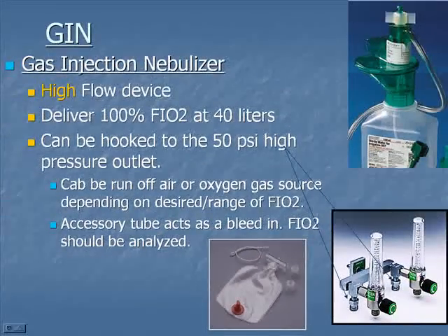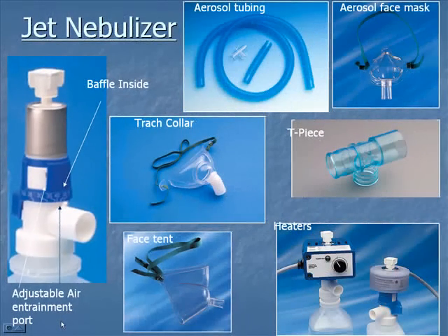Without a collection bag, water builds up in the tubing and will actually spit out of the jet nebulizer port onto the floor. Water spitting out indicates back pressure — the floor can be soaking wet if the tubing hasn't been drained. You can typically hear the difference — it makes a spitting noise as water is pushed out of the jet because of back pressure.